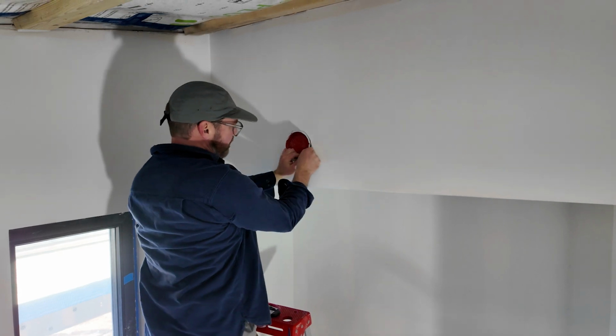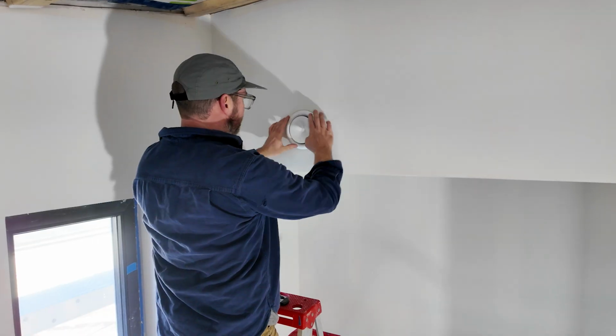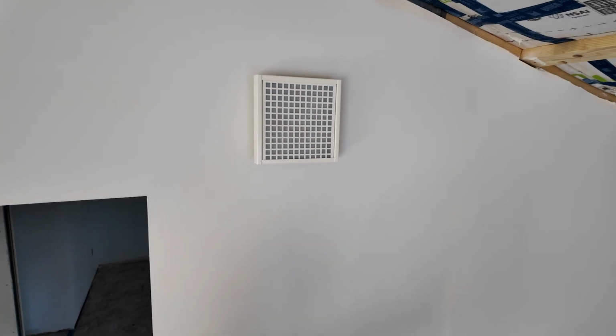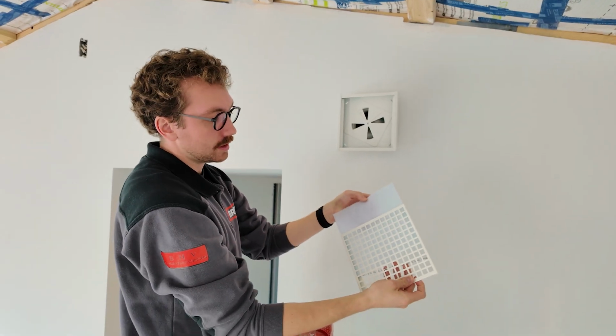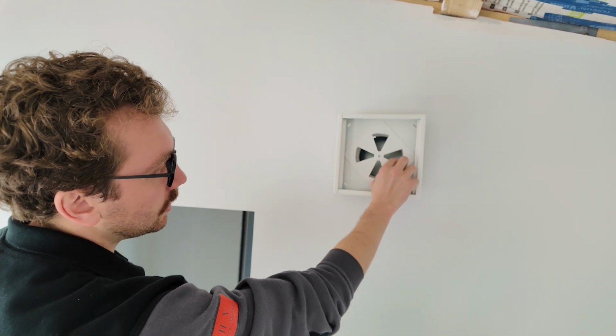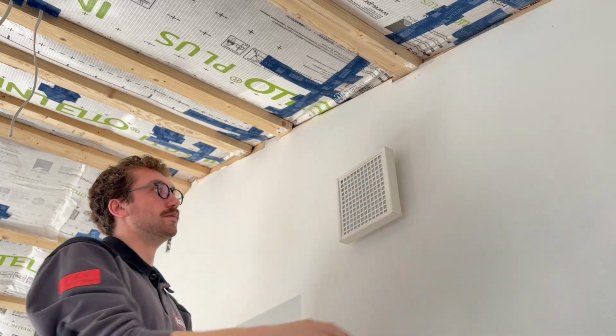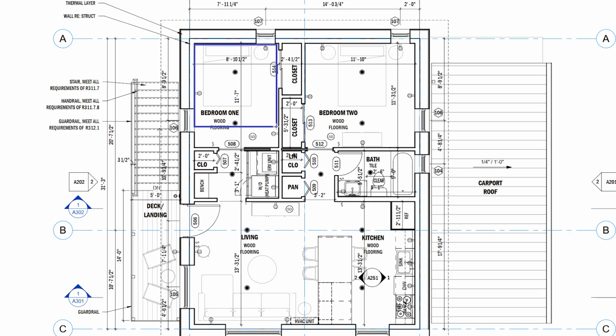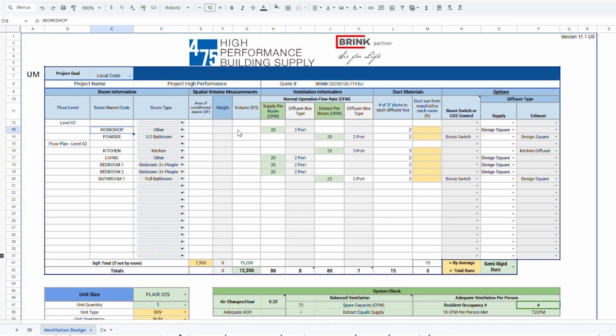As the agent goes around the site, they should fully open all diffusers, and the kitchen filter should be clean to ensure minimum static pressure in the duct system, important for keeping the system efficient. Be sure to record all findings on the commissioning sheet. Reference the floor plans and consult with the responsible party on site to properly identify which rooms correspond to those listed on the commissioning sheet, in case of bedroom 1 versus 2, and that the same number of ducts listed on the commissioning sheet have been connected to their respective diffusers.